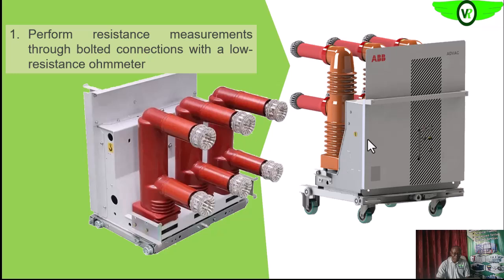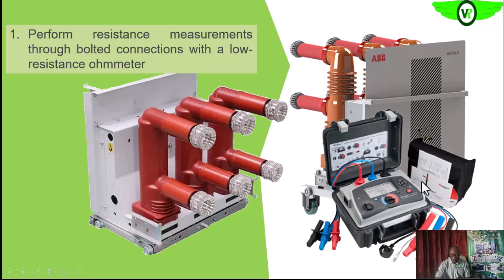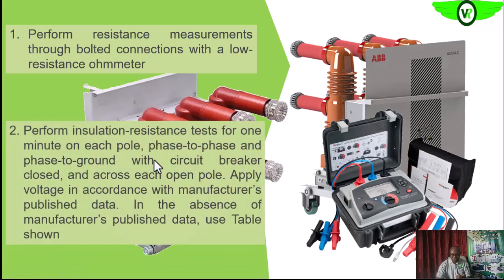We also want to perform the resistance test on bolted connections, the ones that we can access. But if not, then we can let go. We are to use a low resistance ohm meter. On the contact resistance, as we'll see later, we need to close the breaker. Once it is closed, we test across the phase. We need the resistance to be as close to zero as possible. The closer to zero the better. That will give us the contact resistance. As resistance builds between the contacts in the vacuum bottle, that will increase the resistance.